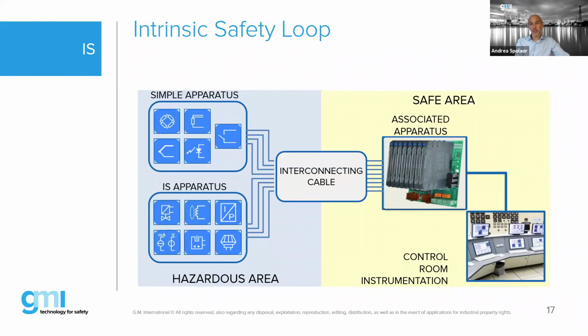The way to control this is to use these barriers, intrinsic barriers, or Zener barriers, which are installed basically in safe areas and can power and read signal in a hazardous area. The way to do that is by controlling the energy in the hazardous area and giving a signal which is safe to the control room instrumentation. You can say that basically in the control room instrumentation there are DCS or PLCs already with intrinsically safe inputs - that's fine. But in case you don't have that, in most cases you have to use that kind of hardware to interconnect the hazardous area to the safe area signals.